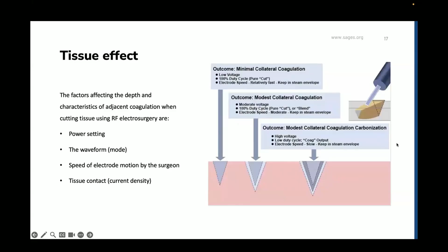Coaptive coagulation. This just means that you are pressing the jaws of an instrument against a vessel to bring both sides together and try to coagulate it, or to achieve hemostasis. At least it was surprising to me to learn that it's actually more efficient or better to use the cut mode when you're trying to achieve this, rather than the coag mode. And I'll show you how and why.